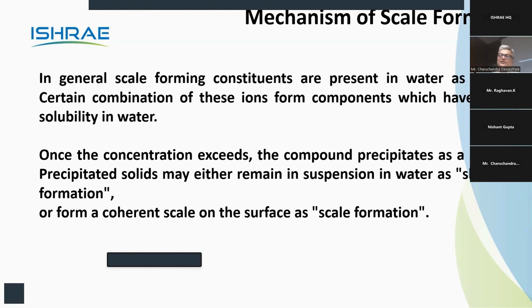Same is the case with cooling water. Whenever the TDS in cooling water gets concentrated over time, those concentrated salts are taken off through a blowdown, and new fresh water comes inside. This new fresh water is called makeup water. The water leaving the cooling water basin as blowdown is called blowdown water. This new water has a very low TDS value, so combining these two, the reasonable TDS figure emerges, which is well within the governing scale.